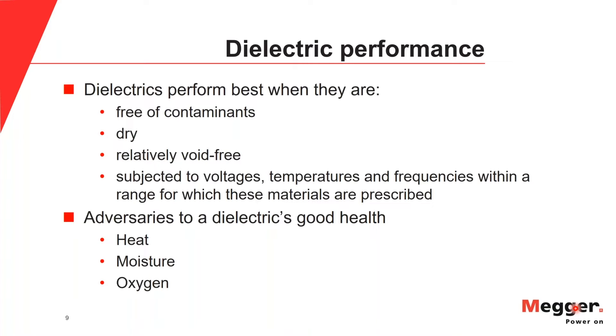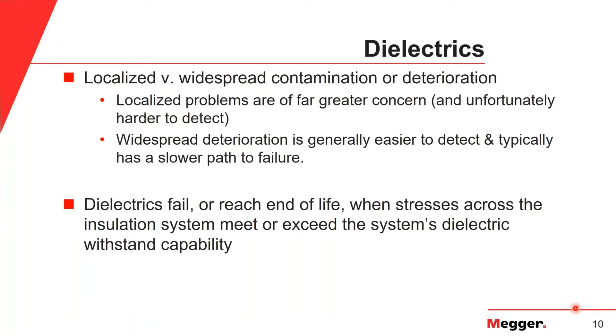Dielectrics work best when subjected to voltages and temperatures within the range for which these materials are prescribed. The major enemies that undermine an insulating material's continued good performance are temperature, water, and oxygen. Areas of localized overheating can sometimes result in a localized dielectric problem where materials throughout the rest of the system can retain their starting properties. Localized problems are a far greater concern than widespread deterioration, but unfortunately they are much harder to detect. Dielectrics fail when the stresses across the insulation system meet or exceed the system's dielectric withstand capability.